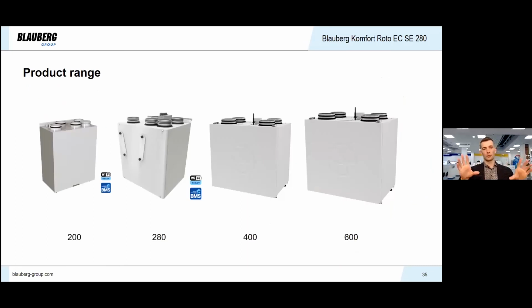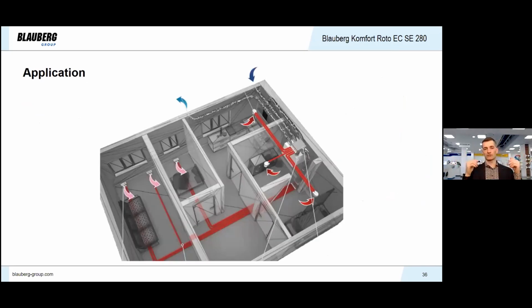On this slide you can see the model range in brief. There are 4 units and the nominal airflows are 200, 280, 400 and the maximum one is 600 cubic meters per hour. So this is more than enough for residential application. If you have a commercial application, you can refer to the Blauberg unit that we were talking about at the beginning of this part. So let's proceed. Typical application, of course, and here we can see once again an apartment, but as you can see, the ventilation system differs a little bit. There is a line here. The kitchen hood is connected directly to the unit.